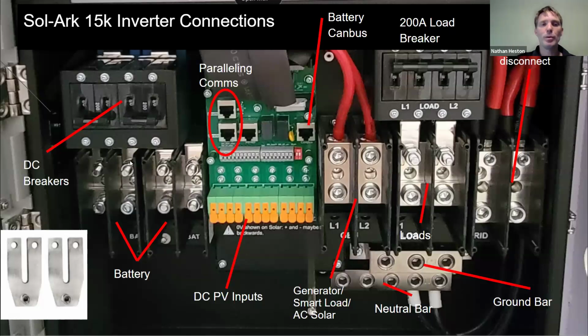With big battery banks, people are typically using 4-aught cabling, and so if you don't want to have to make some kind of combiner or use some Polaris connector, etc., compression connector to join and split your cabling, you can buy these bus bars that I've shown in the bottom left-hand corner and just combine those 200 amp breakers into single positive input and negative inputs. These are the DC breakers in the top left side. This is what you will turn on and off to connect and disconnect your battery from the Sol-Ark 15K. In the center of the screen, you see the paralleling communications ports.